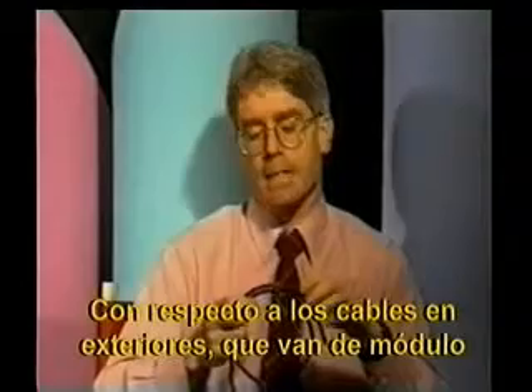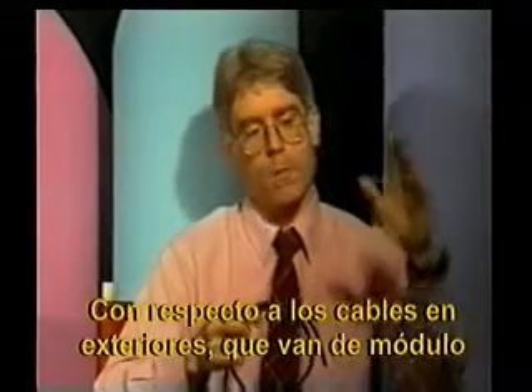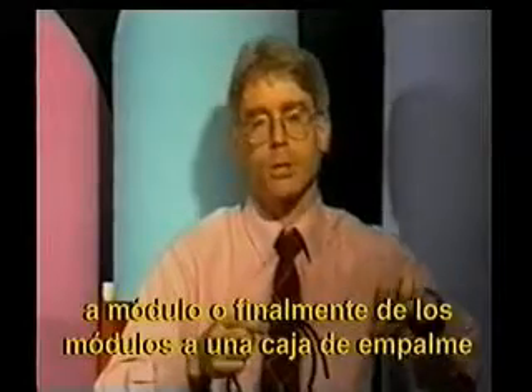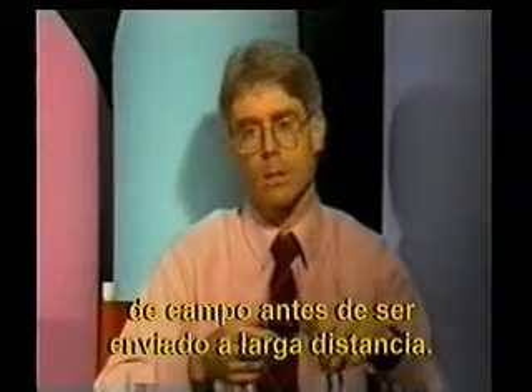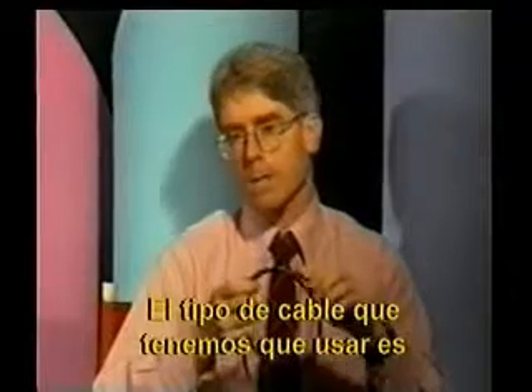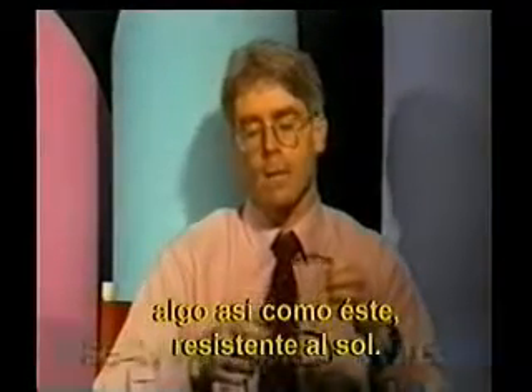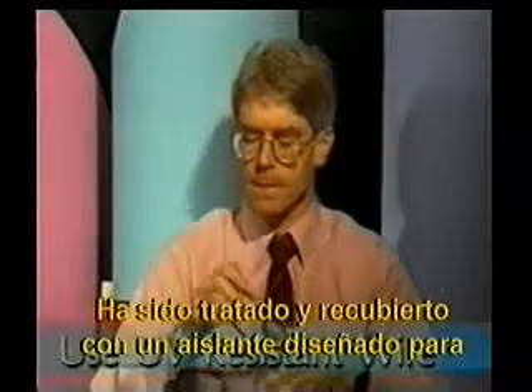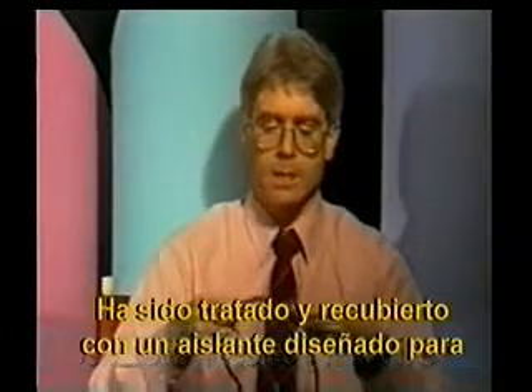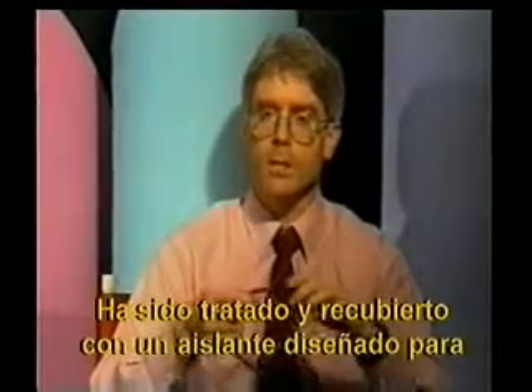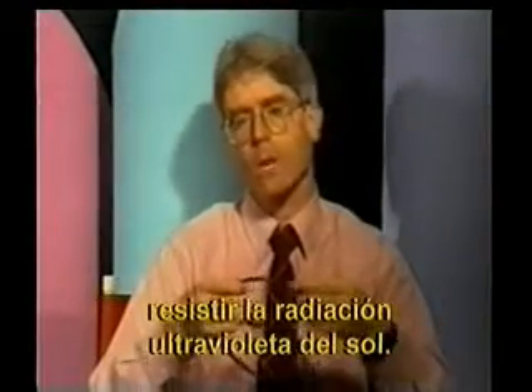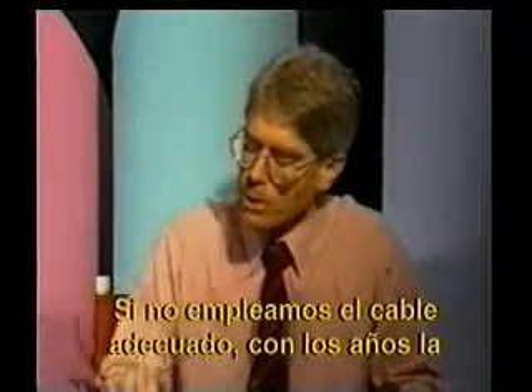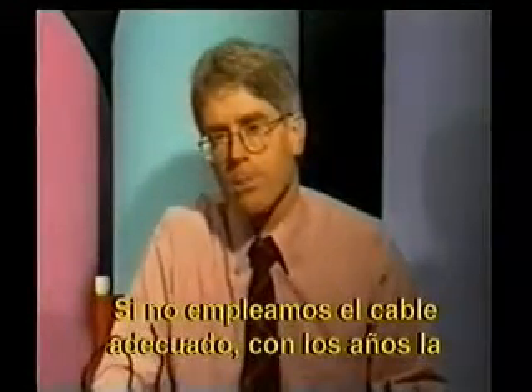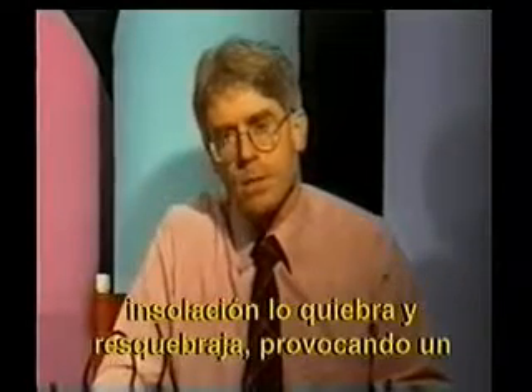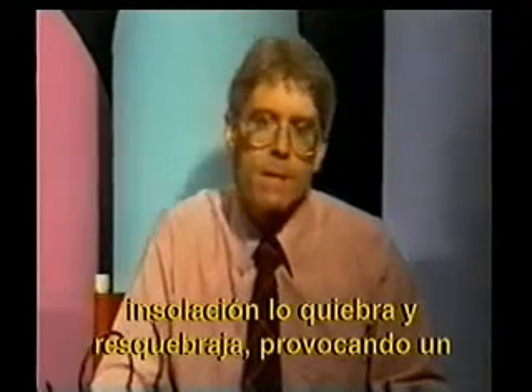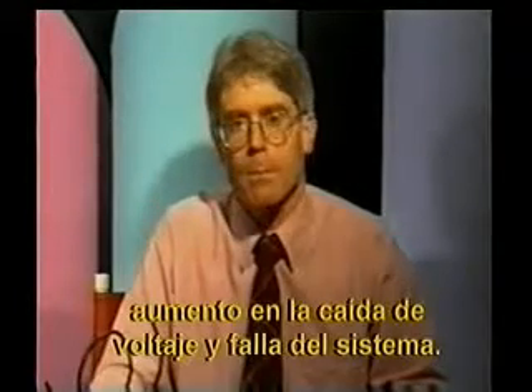In terms of looking at outdoor wiring, the wiring that goes from module to module or finally from the modules into a field junction box before it's sent a long distance, the type of wire that we need to use is something like this wire, sunlight resistant wire that's specifically been treated and coated with an insulation that's designed to withstand the ultraviolet radiation from the sun. If we don't use the proper type of wire, over years the insulation will crack, become brittle, and break away. And that could lead to increased voltage drop and system failure.